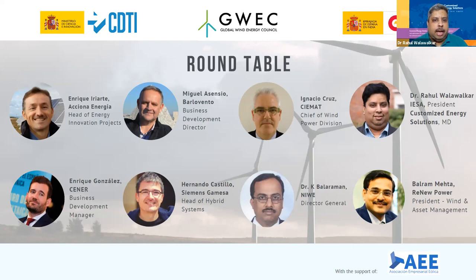So in terms of sizing, it would depend on the application. Dr. Balaraman mentioned the deviation settlement mechanism and some of the penalties coming in. So if the focus is purely on minimizing those penalties, you can probably just work with 1 hour of storage. For such applications, typically we've seen around 30% of the power rating with 1 hour storage that can work.